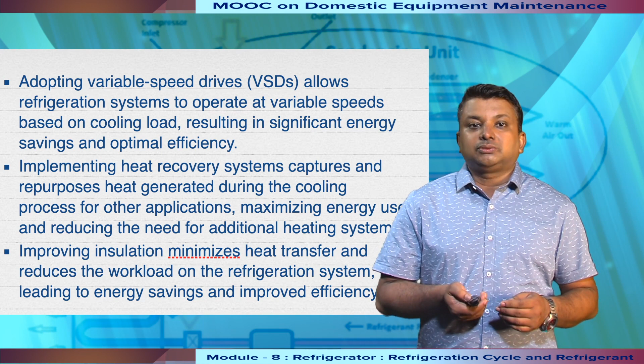Another strategy to improve energy efficiency is through the implementation of heat recovery systems. In refrigeration systems, heat is typically released during the cooling process. Instead of wasting that heat, it can be captured and repurposed for other applications such as space heating or water heating. By utilizing heat recovery systems, businesses can maximize the use of available energy and reduce the need for additional heating systems, resulting in energy savings and more sustainable operations.